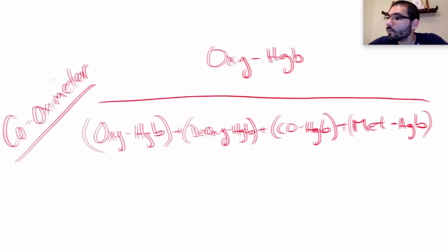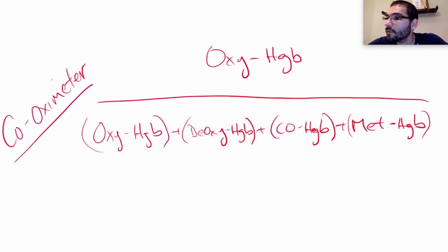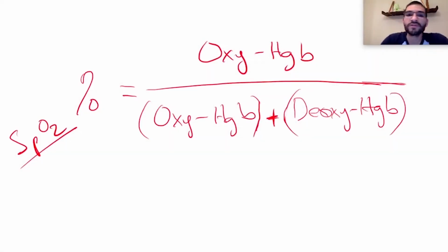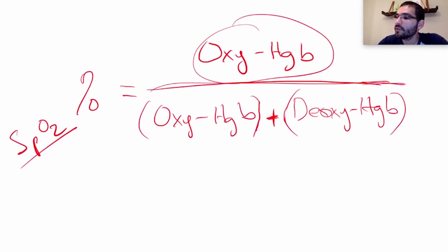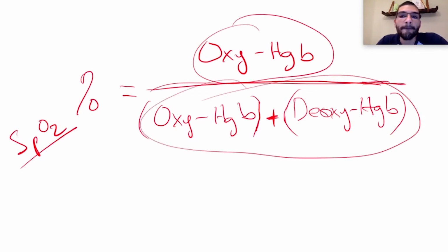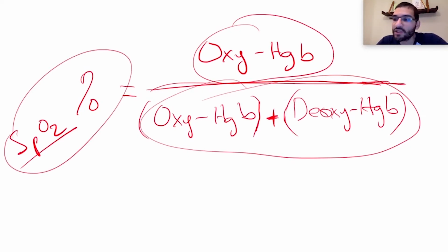Let me bring this up here. That's not the one. I apologize. A pulse oximeter, as you can see, measures oxyhemoglobin and then divides it by the total hemoglobin, oxy and deoxy. You get from here some oxygen percentage status, but it assumes that you don't have any methemoglobin or any carboxyhemoglobin or any other types of dyshemoglobinemias, which is not necessarily true, right?